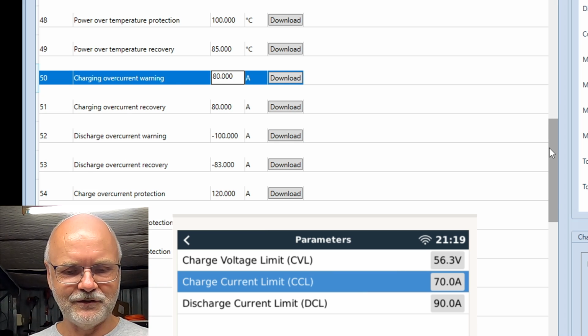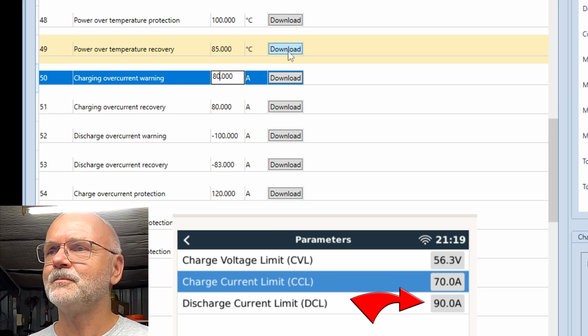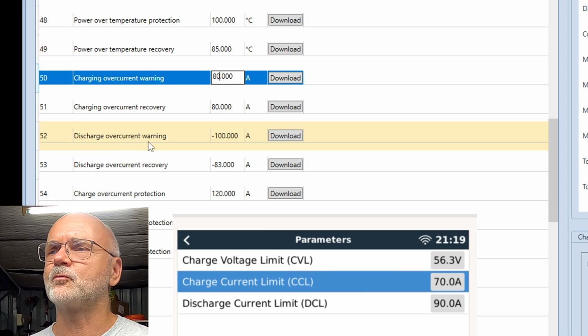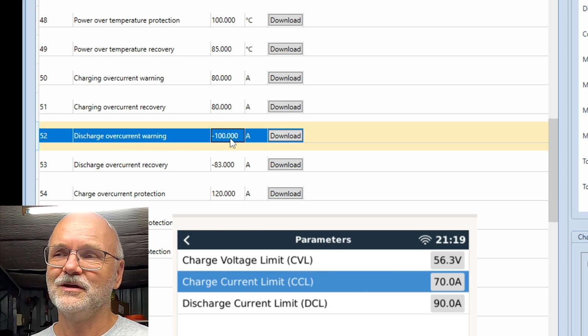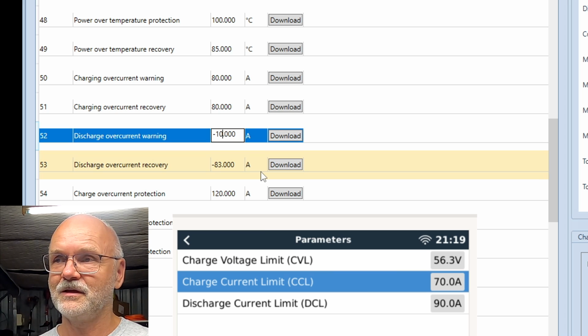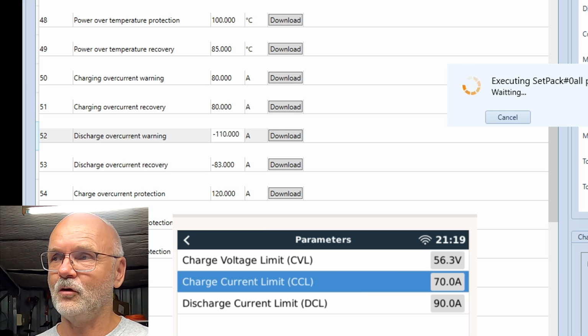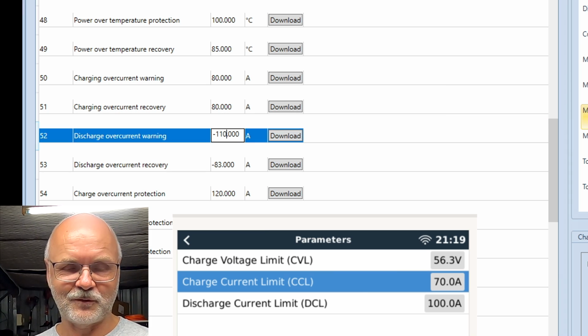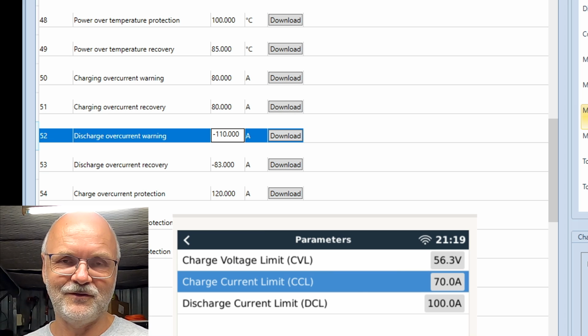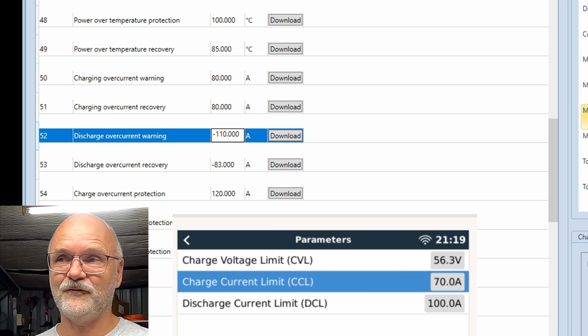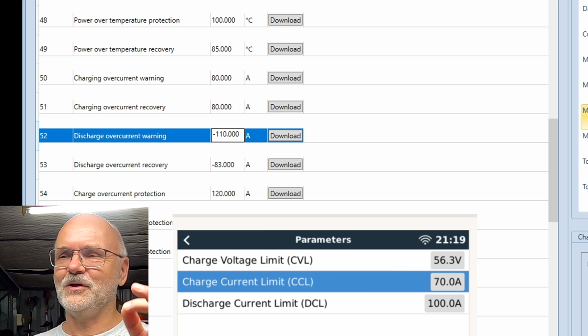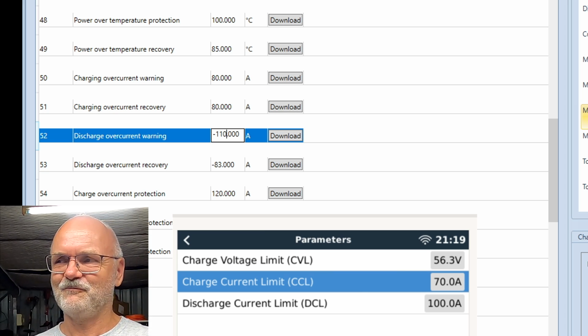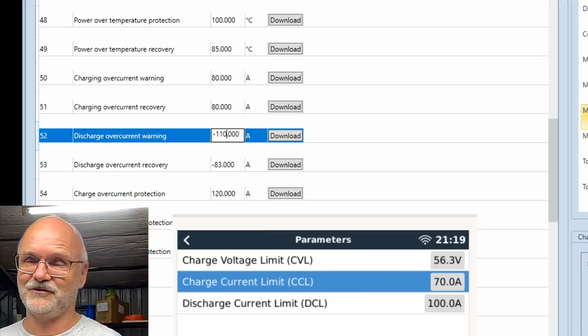And the discharge current limit in the Victron system sits on 90. You have to find the discharge overcurrent warning. This sits on 100 amps. So it looks like they're using the same formula for both here in this older BMS. So if I set this one to 110 amps, set all, yep, success, and this one changes to 100 amps in the Victron system. So it's the same formula here for charging and discharging, which makes sense. But it's a different formula for the 10C BMS, for whatever reason, we don't know. It is what it is.